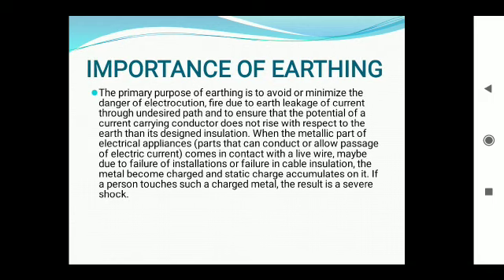Now the importance of earthing. The primary purpose of earthing is to avoid or minimize the danger of electrocution, fire due to earth leakage of current through undesired path, and to ensure that the potential of the current carrying conductor does not rise with respect to the earth than its designed insulation.